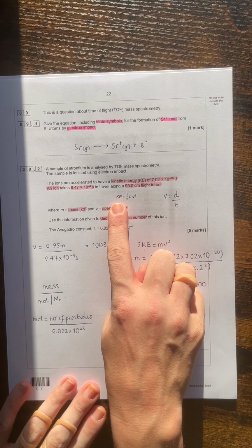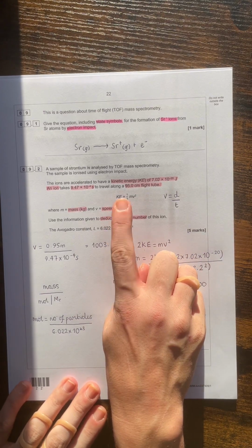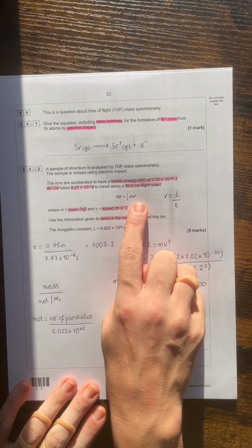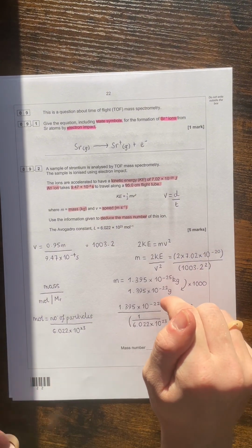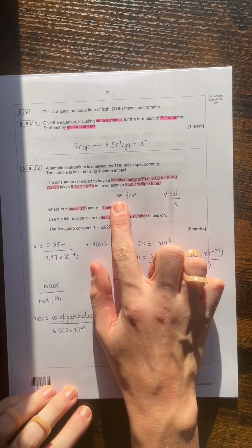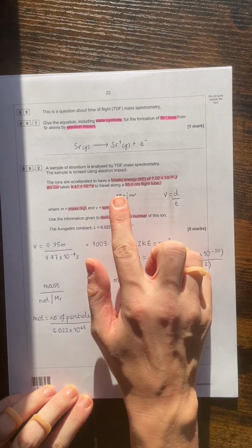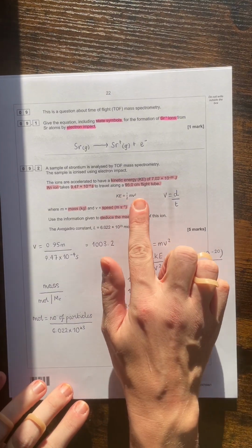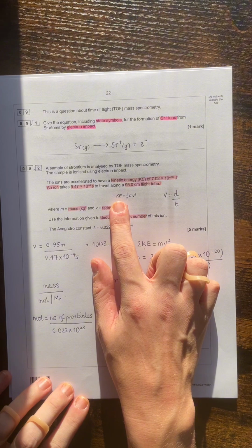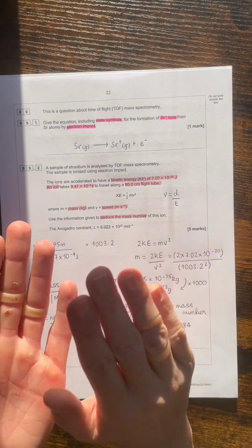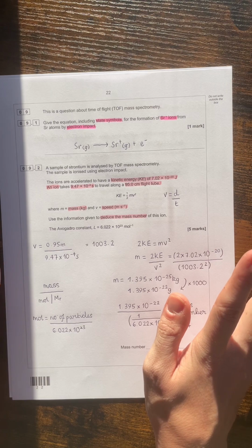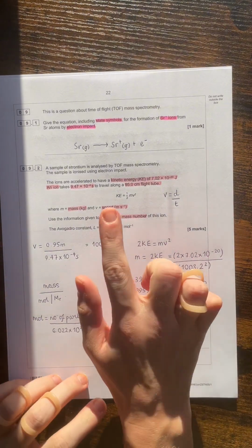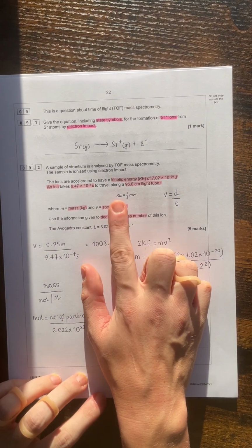And if the kinetic energy of all the ions is the same, the heavier they are, the slower they're going to be. Their velocity will lower as their mass increases, and that's how we can measure those, because we're keeping the kinetic energy the same. We can therefore compare the mass and velocity of all the different isotopes for a particular element. So it's really important that all the ions have the same kinetic energy.